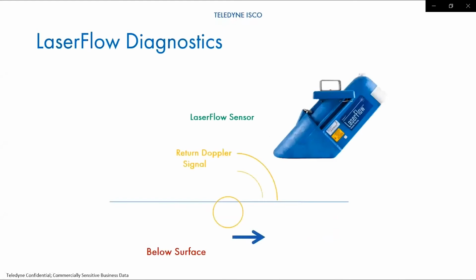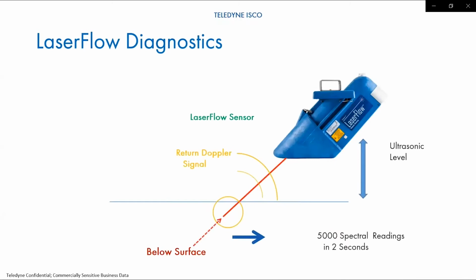Other options, if you have silting, switch to a non-contact sensor, such as the LaserFlow sensor, because this will use the ultrasonic sensor to read the distance to the water. It calculates the level for your flow calculation, transmits a laser below the surface of the water. And the difference here is actually reading the peak velocity. It takes 5,000 spectral readings in 2 seconds to get your peak velocity to then calculate your average velocity for your flow rate. And it will also determine the frequency shift and the speed of the water.